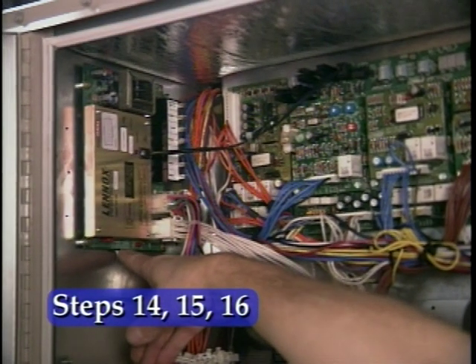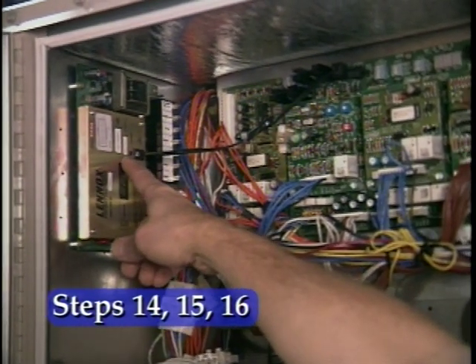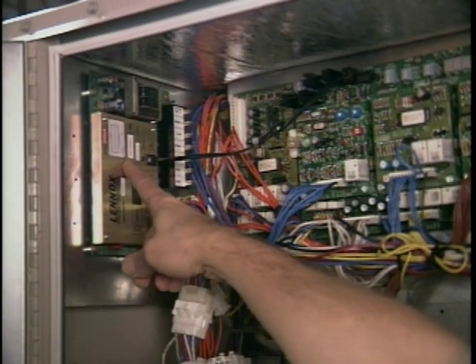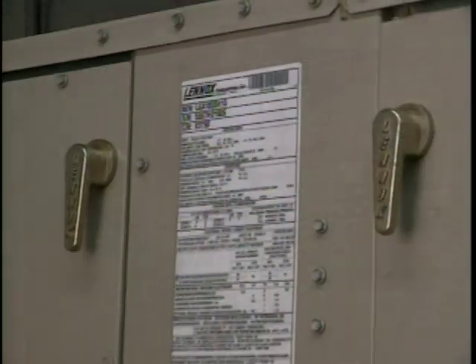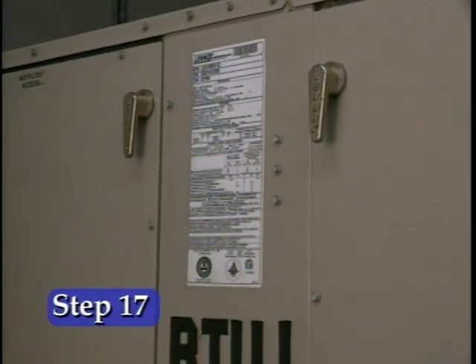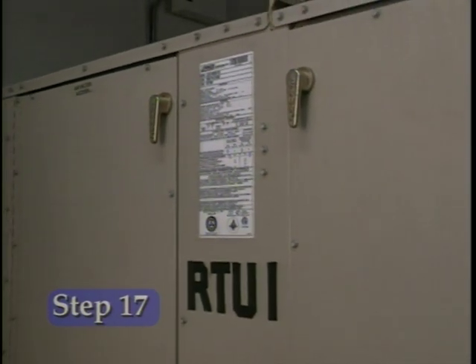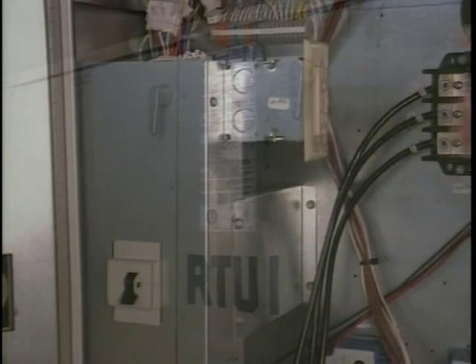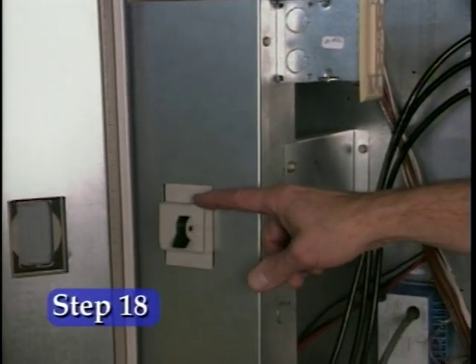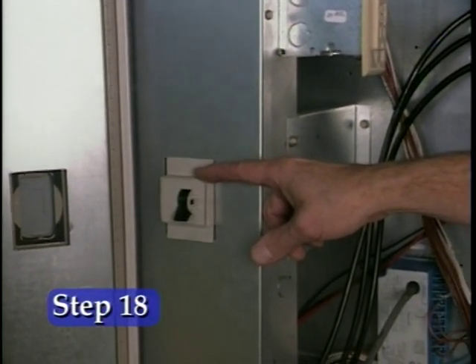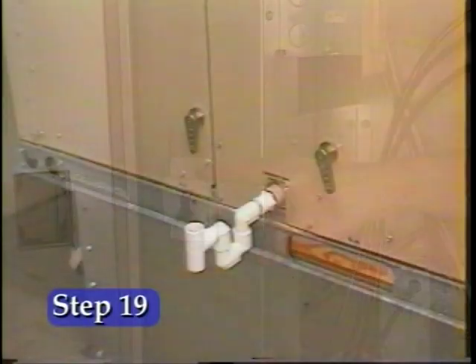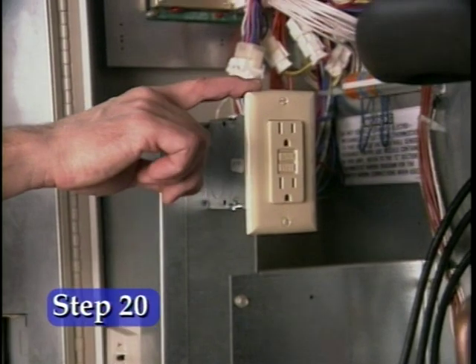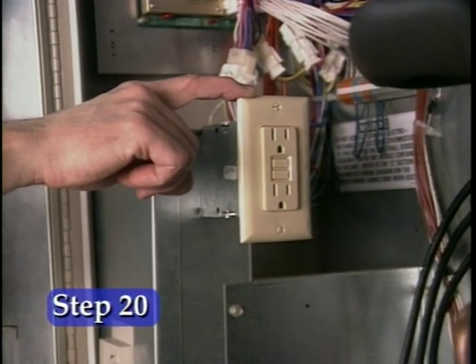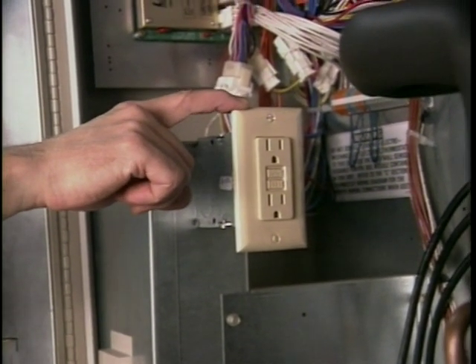Record the control system information found on the DDC controller mounted inside the unit just to the left of the IMC board. The installing contractor should have painted the RTU number on or attached a nameplate with the RTU number to the unit. The electrical disconnect may be factory or field installed. Check the appropriate type. Check that a vented trap is installed on the condensate drain. The unit may include a convenience outlet. It must be field wired to 120 volts. If there is no outlet, check NA.